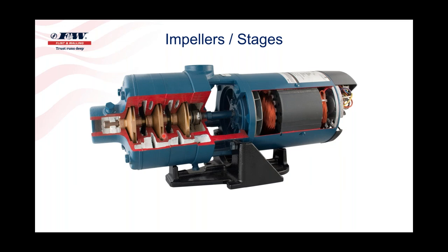They come through as larvae, and they go inside the pump, and they grow, and they multiply, and they reproduce, and they form these shells, and as this pump turns and powers on, it crushes all these shells. They become extremely abrasive, and they shred my impellers. I imagine those brass impellers will work a lot better, won't they?